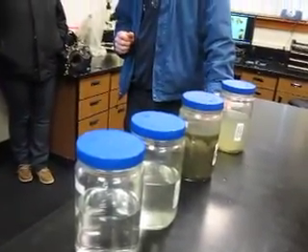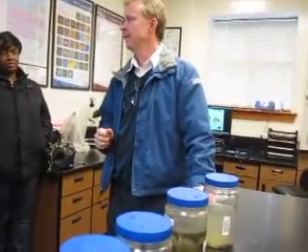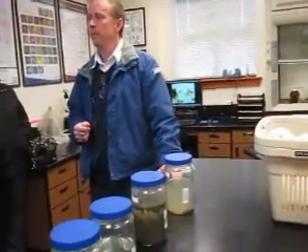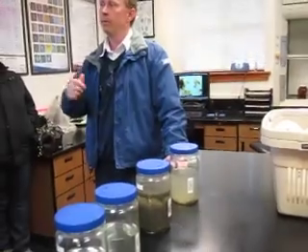Golly, any questions? I need a break. How long does it take from water in to water out? That's a very good question. We call that detention time. What's the detention time through the plant? Well, on an average daily flow basis, I would say it's probably 14 to 16 hours from front to back.